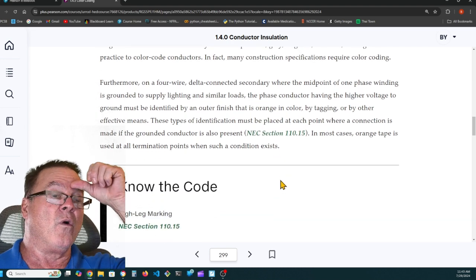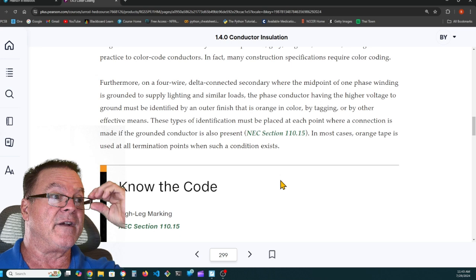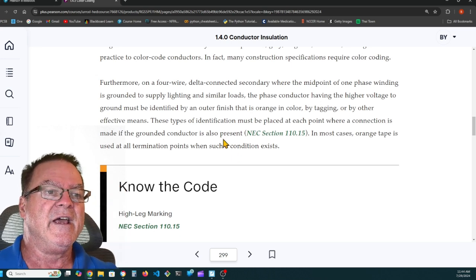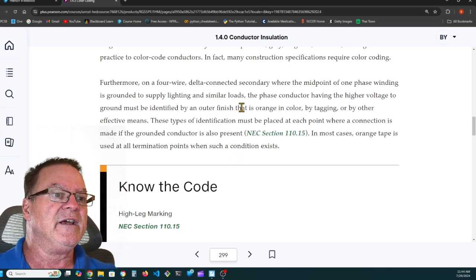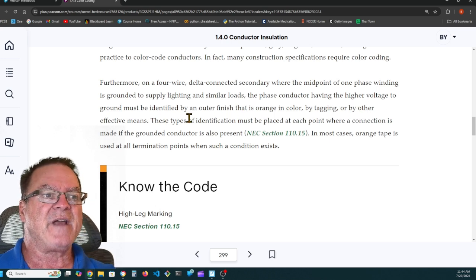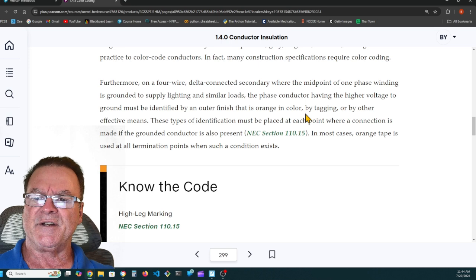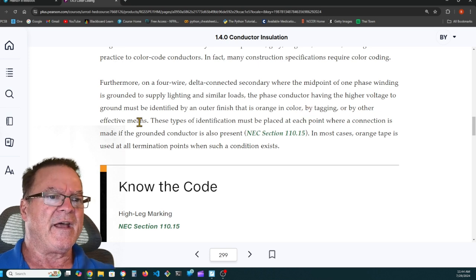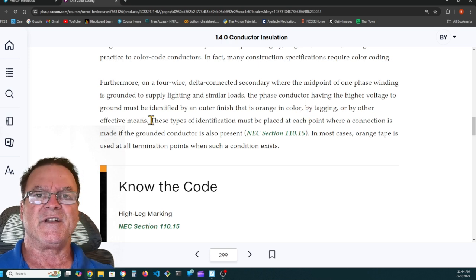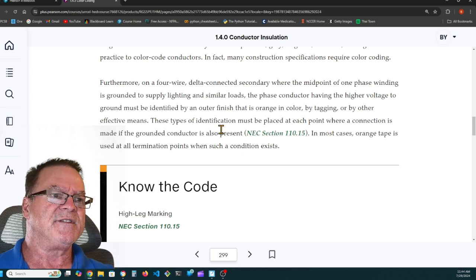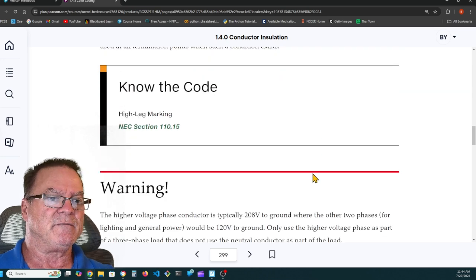Furthermore, on a 4-wire delta connected secondary, where the midpoint of one phase winding is grounded to supply lighting and similar loads, the phase conductor having the higher voltage to ground must be identified by an outer finish that is orange in color. They call that the high leg or the stinger leg. That high leg has to have an outer finish that is orange. These types of identification must be placed at each point where a connection is made if the grounded conductor is also present.